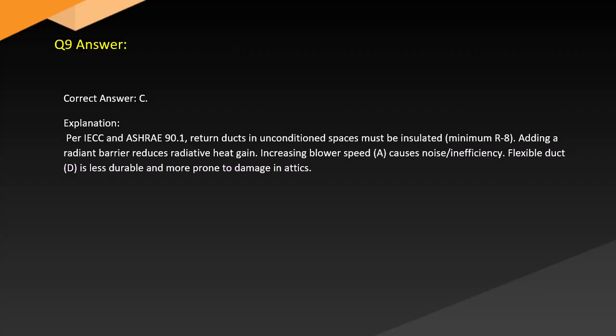Answer. Correct answer: C. Explanation: Per ASHRAE 90.1, return ducts in unconditioned spaces must be insulated, minimum R8. Adding a radiant barrier reduces radiative heat gain. Increasing blower speed, A, causes noise and inefficiency. Flexible duct, D, is less durable and more prone to damage in attics.